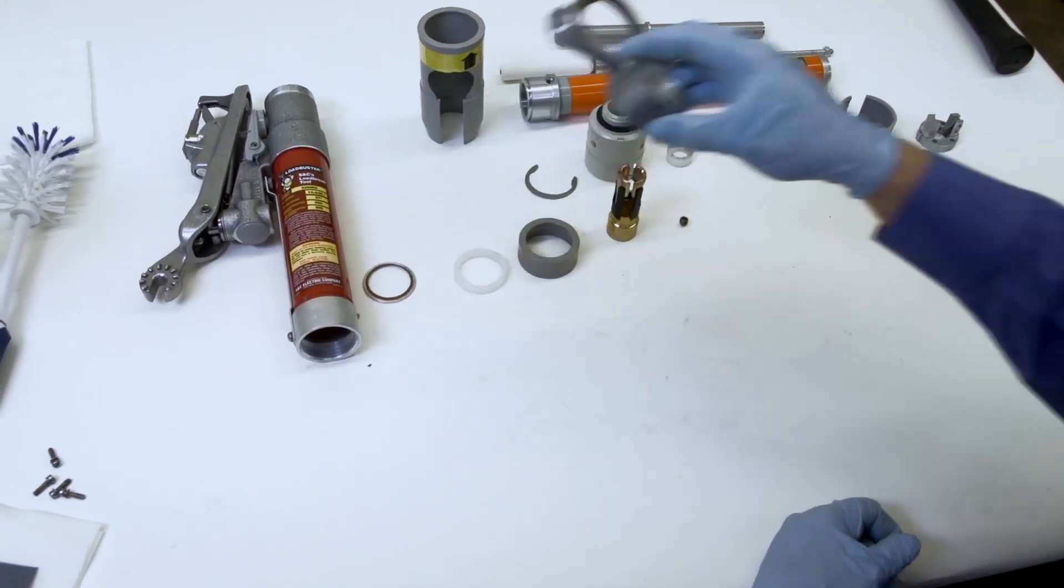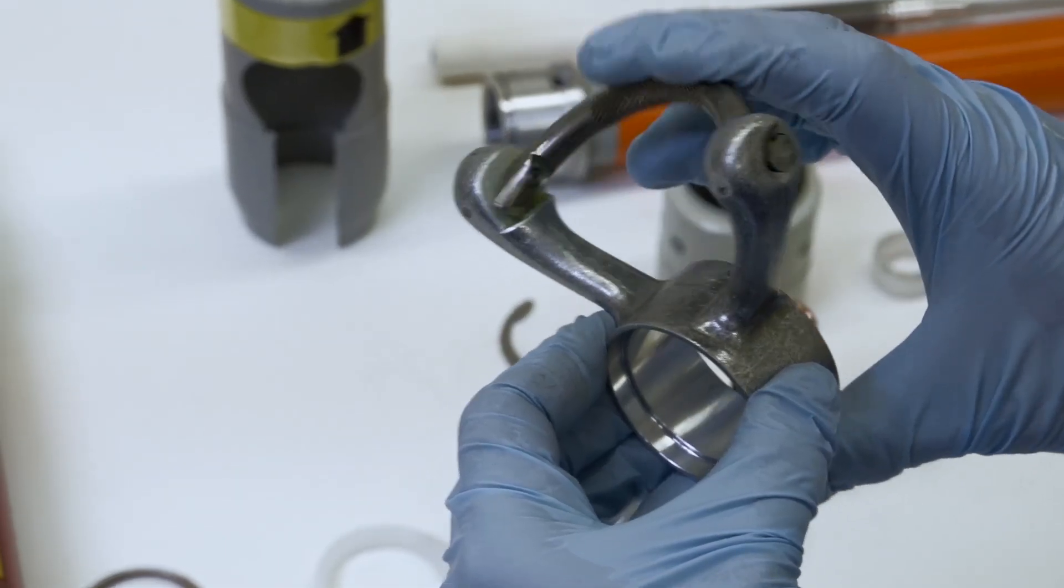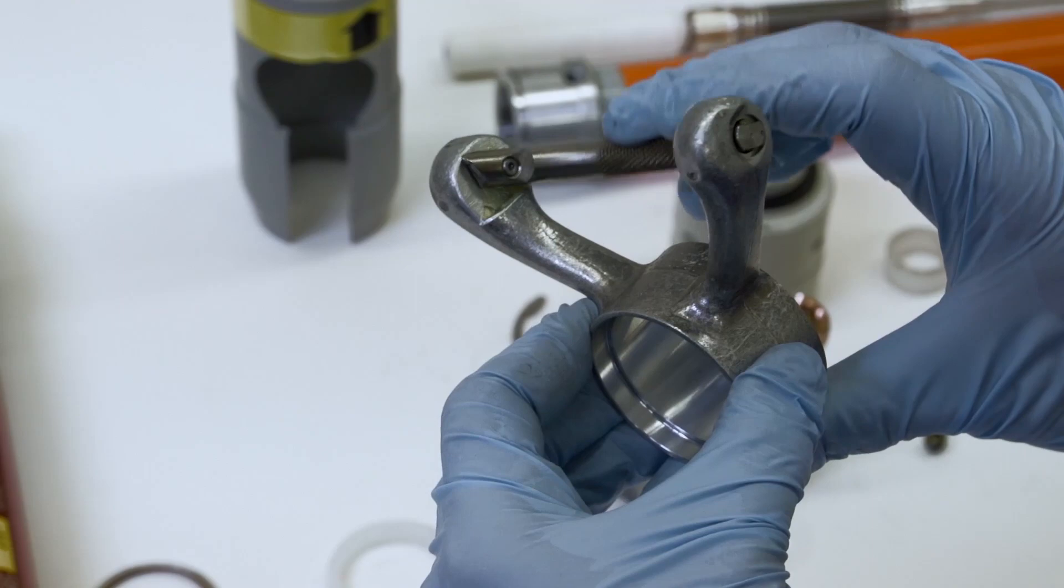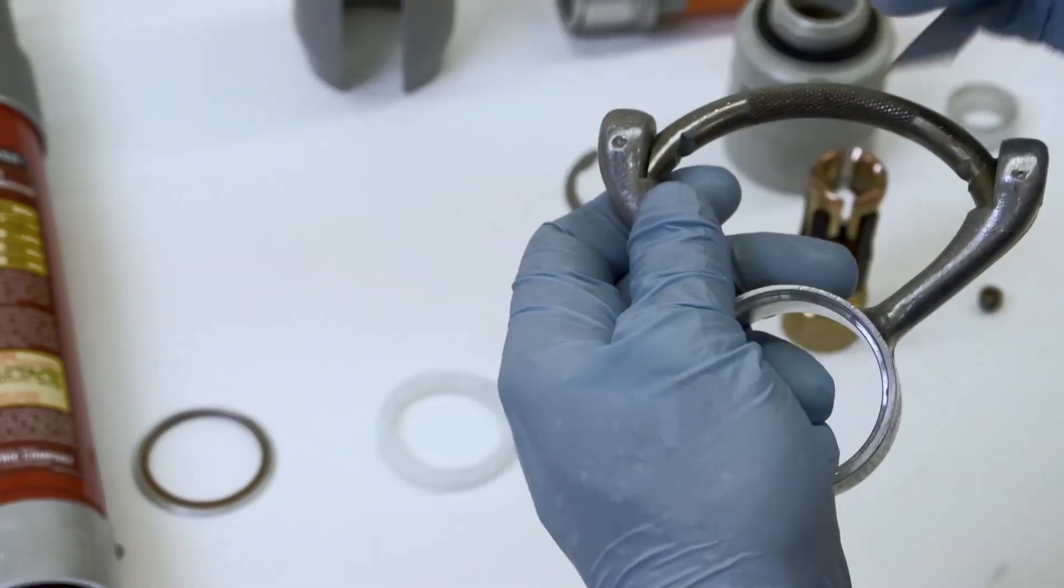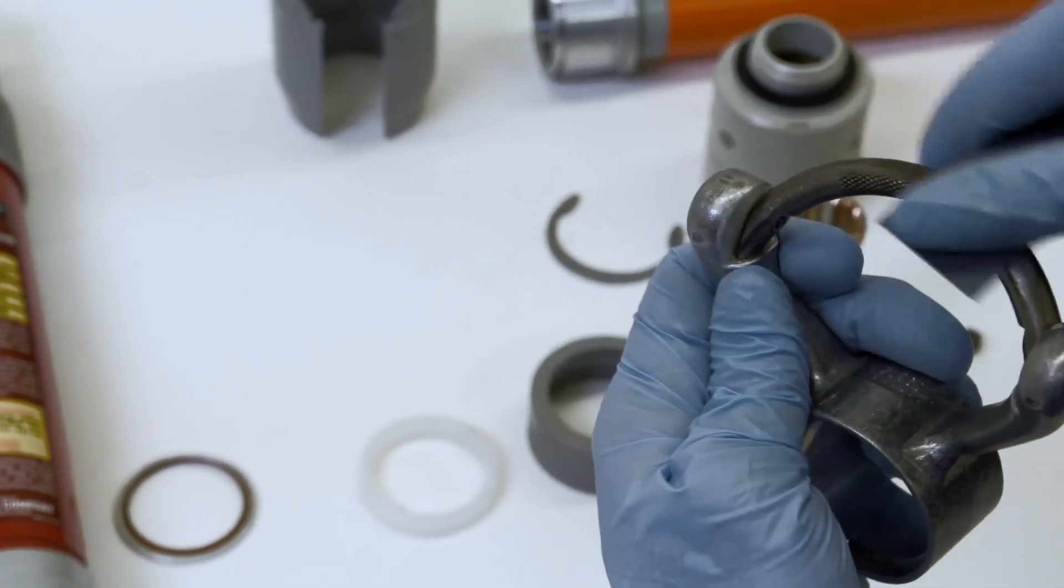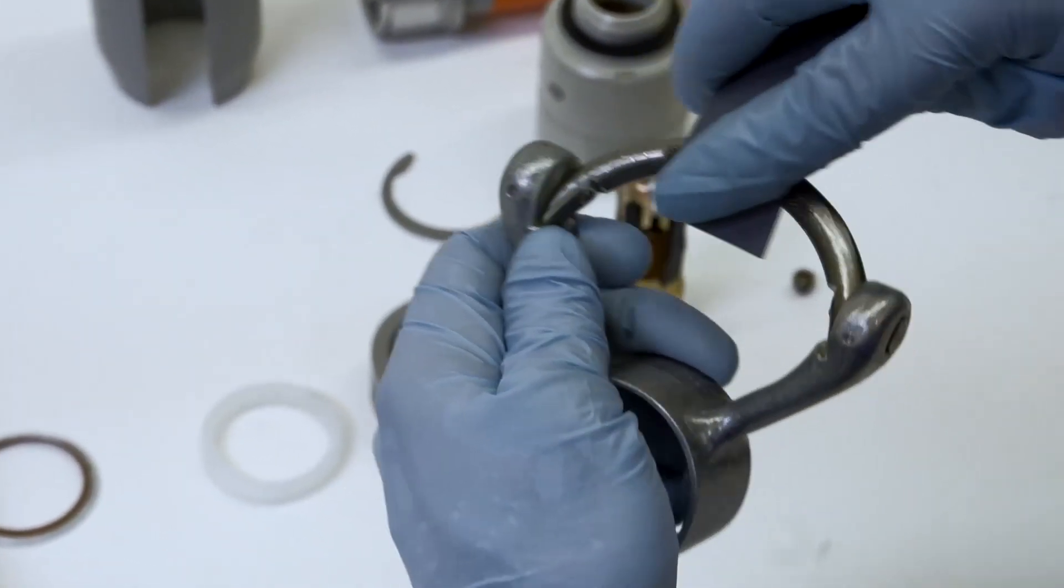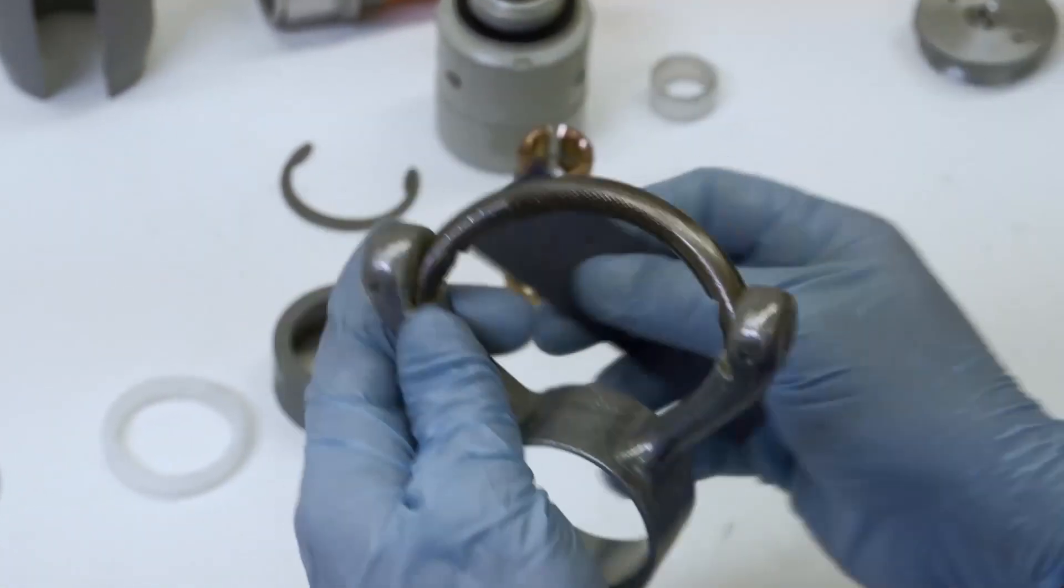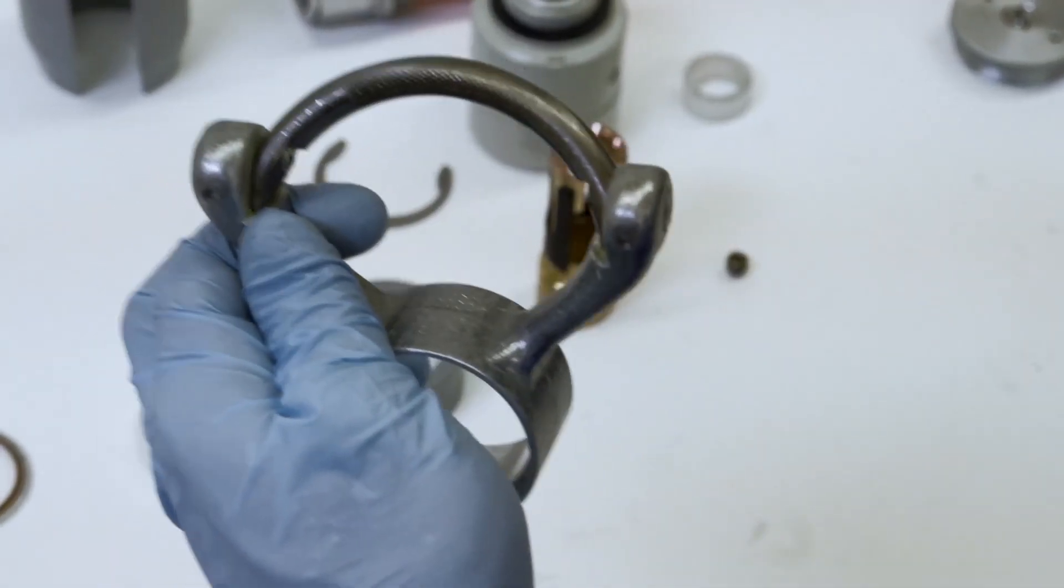Next we'll examine the anchor assembly. The assembly is spring loaded and should snap back when pulled. Polish the anchor assembly with an emery cloth to remove pitting. If severely pitted, burned, or if the spring does not work, the anchor assembly should be replaced.